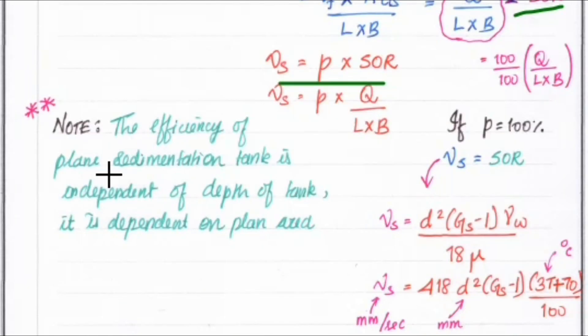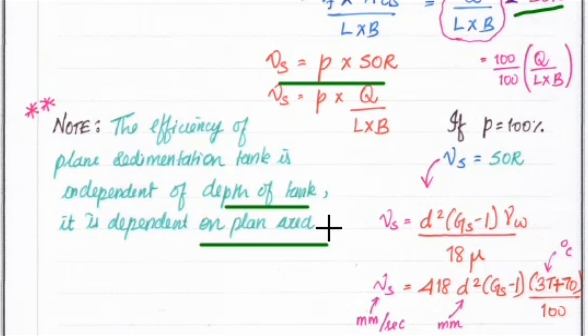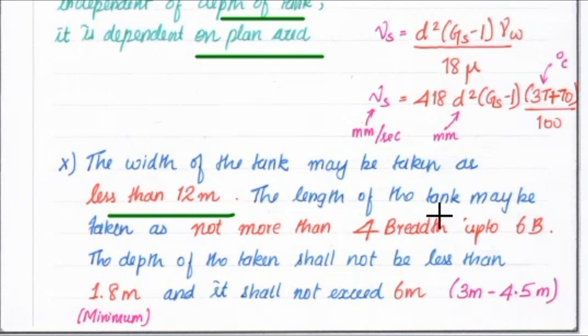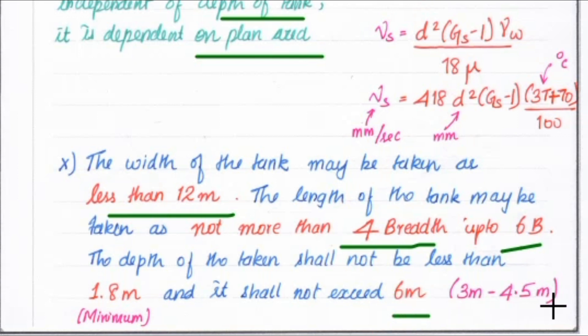It is important to note that the efficiency of the plain sedimentation tank is independent of the depth of the tank — it depends upon the plan area. The settling velocity formula (Stokes' law) is: Vs = D² × (Gs − 1) × γW / (18 × μ), or equivalently Vs = 418 × D² × (Gs − 1) × (3T + 70) / 100, where T is temperature. Design constraints: the width of the tank may be taken as less than 12 metres; the length shall not be more than 4B to 6B; and the depth shall not be less than 1.8 metres and shall not exceed 6 metres, typically 3 to 4.5 metres.